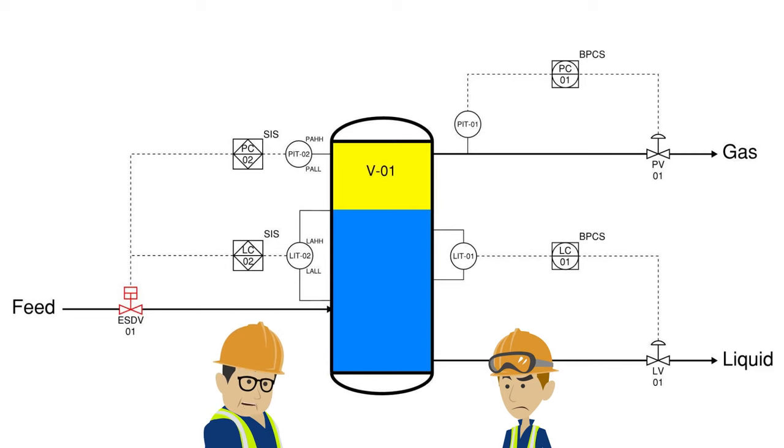If the level in the vessel gets too high, there's a potential to carry liquids over to the compressor downstream on the gas system. This could cause a catastrophic failure in the compressor.